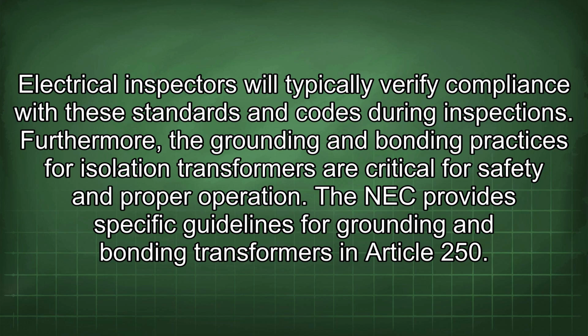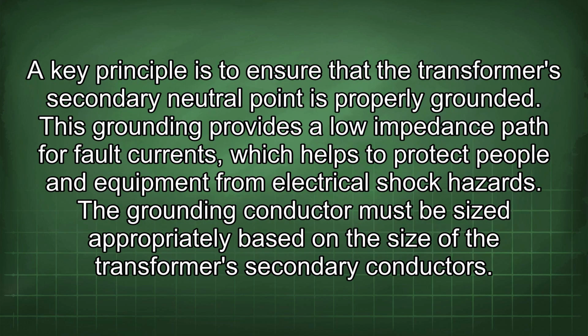Furthermore, the grounding and bonding practices for isolation transformers are critical for safety and proper operation. The NEC provides specific guidelines for grounding and bonding transformers in Article 250. A key principle is to ensure that the transformer's secondary neutral point is properly grounded. This grounding provides a low impedance path for fault currents, which helps to protect people and equipment from electrical shock hazards. The grounding conductor must be sized appropriately based on the size of the transformer's secondary conductors.